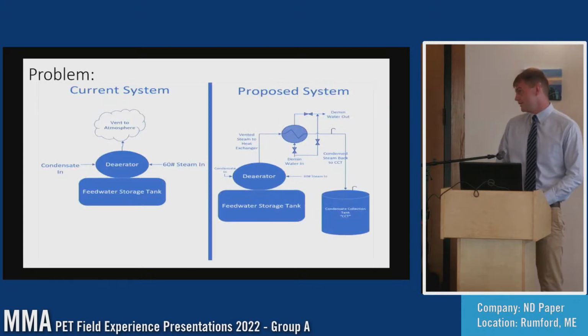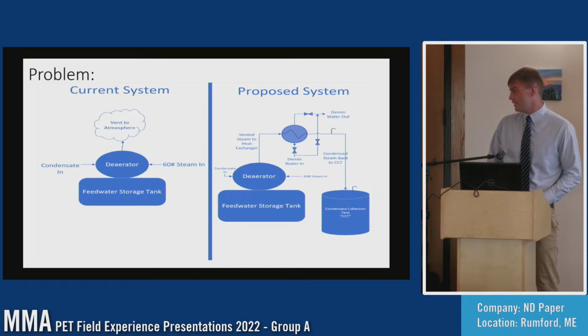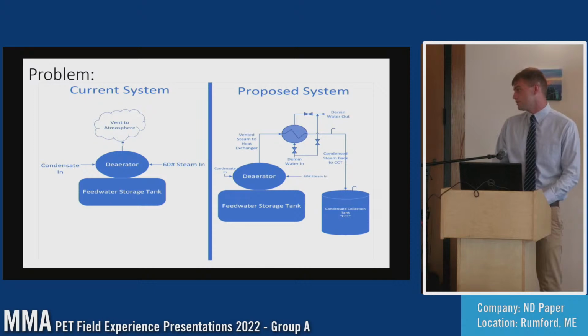So for the problem I had, as we all know, Rumford emphasizes efficiency. It's our main priority. And so my problem was to analyze putting a heat exchanger on the DA vent. On the left is what we currently have, which is your standard DA. And then on the right is putting a heat exchanger, which has demin water going through it on the other side, and also having vents to get all your NCGs out, and then having your condensed steam go back into the condensate collection tank for reuse.